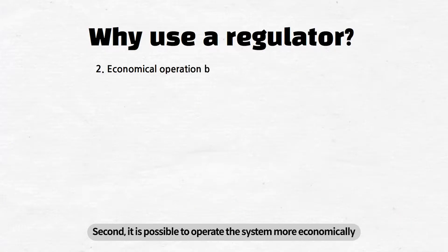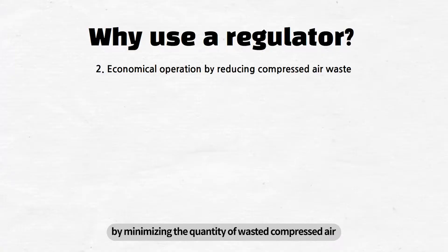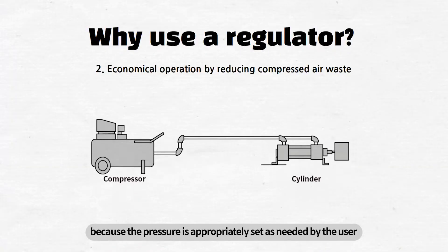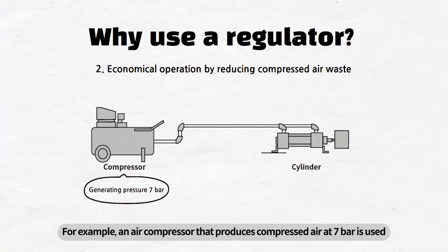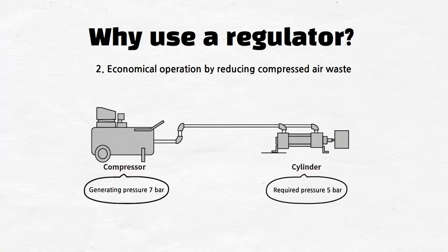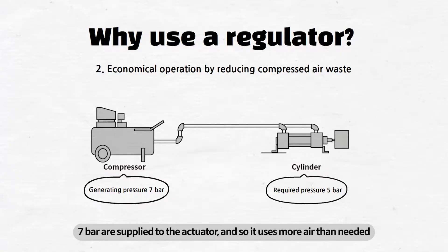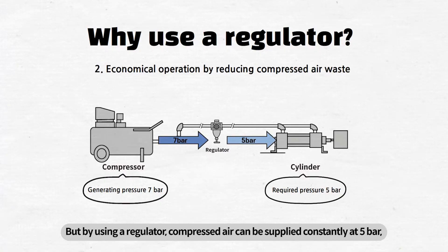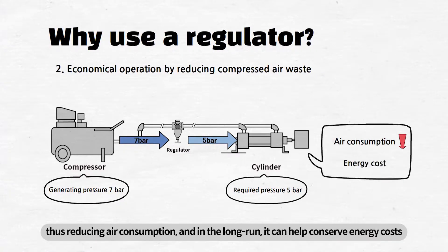Second, it is possible to operate the system more economically by minimizing the quantity of wasted compressed air. Waste of compressed air is reduced because the pressure is appropriately set as needed by the user. For example, an air compressor that produces compressed air at 7 bar is used, and let's assume that the pressure needed for operating the actuator is 5 bar. If a regulator is not used, 7 bar are supplied to the actuator, and so it uses more air than needed. But by using a regulator, compressed air can be supplied constantly at 5 bar, thus reducing air consumption, and in the long run, it can help conserve energy costs.